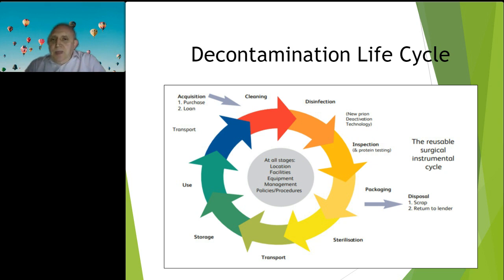So in my experience, this conveyor was not validated. At the end of the shift, some of the larger members of staff would pull the devices through the conveyor. The instruments would not see any water. Well, with the advent of HTM 2030, that went away. Validated washer disinfectors were of the highest importance, and part of that is water quality.